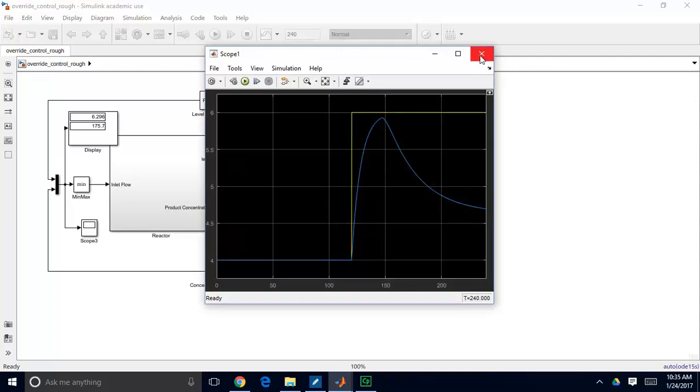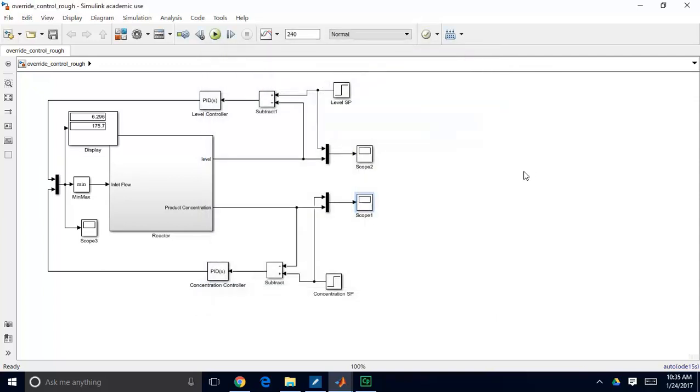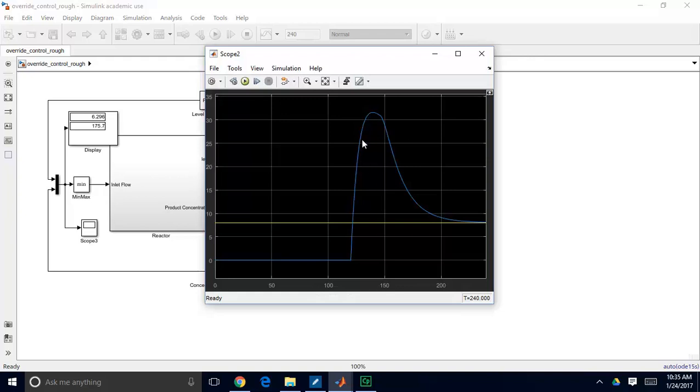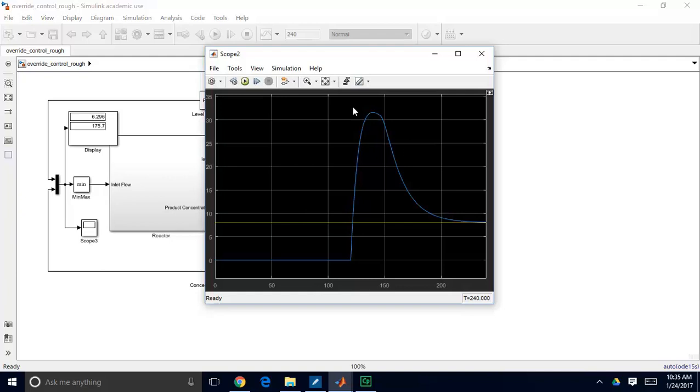So the issue that we ran into was that this concentration controller experienced reset windup, where it's well below its setpoint on level, and it takes a long time for that controller to unwind. In other words, we had to take all the integrated error and we had to subtract all that integrated error before this controller could actually reach its setpoint. So in practice, you can see this is a big problem because if our tank overflowed at 10 meters, we're going way over that level until before the controller actually starts to have a positive effect on our system.